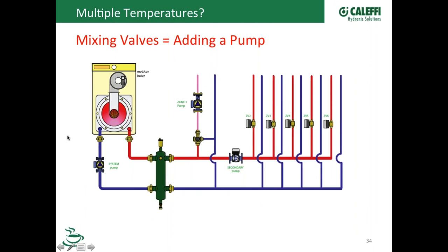This is another one of Cody's clever schematics that he put together when people call and say, well, what if I want to put a low temperature zone out with some high temperature zones? So I'm going to let Cody talk to this a little bit about what he was thinking here. Well, I was going to say, Bob, the golden rule with multiple temperatures is anytime you add a mixing valve, you need to add another circulator.